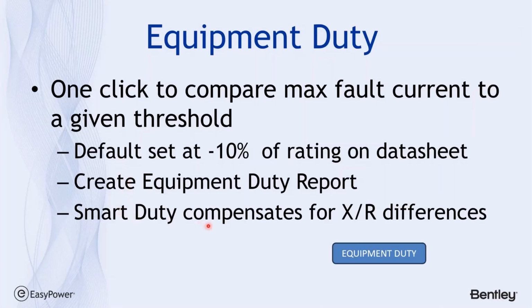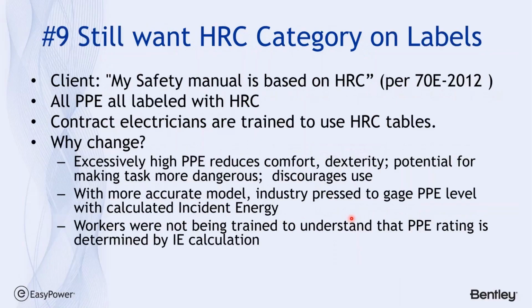And I make a note that SmartDuty compensates for X over R differences. EasyPower calculates the X over R for every bus in the system, and wherever there's a protective device where the manufacturer has tested it within a certain X over R value, EasyPower will compensate so that we're doing an apples-to-apples comparison during this test. Still, I see people come at me and say, my client wants both the HRC category and the incident energy on the label. What should I do?